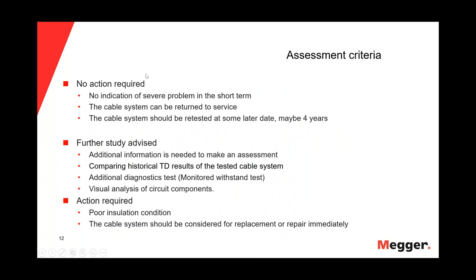Breaking down each action: no action required means no indication of severe problem in the short term — the cable system can be returned to service and should be retested at some later date, perhaps four years. Further study advised means additional information is needed, such as comparing historical Tan Delta results of the tested cable system — for example, if you had data before and after adding a splice. Additional diagnostics tests and monitored withstand tests are also indicated. Action required means poor insulation condition — the cable system should be considered for replacement or repair immediately.